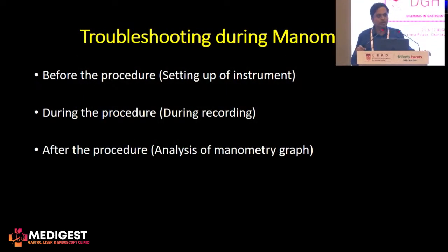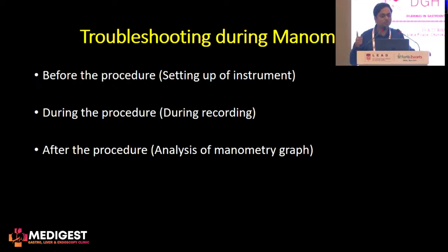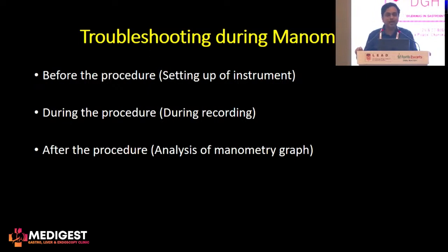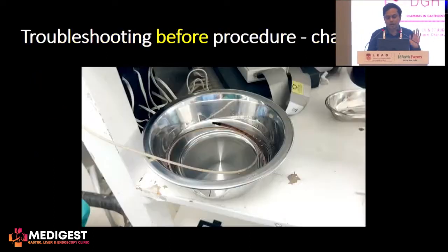Troubleshooting during manometry can be at essentially three steps. First and most important is before the procedure, where we are actually setting up the instrument to see whether it is working right. Second is during the procedure — during the recording of the graphs. Third is after the procedure, when you are analyzing the manometry graph. Troubleshooting is important and can be needed at multiple stages.